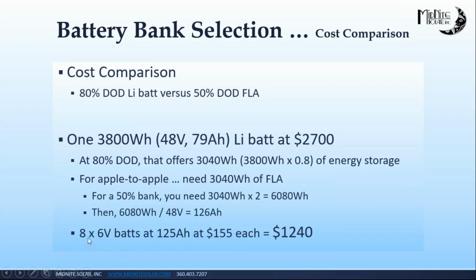That's close enough. So I would buy 8 of these 6-volt batteries and put them in a single series string—positive to negative, positive to negative. 6 times 8 is 48 volts, and each one was $155. So the total cost for those 8 batteries is $1,240 compared to $2,700.